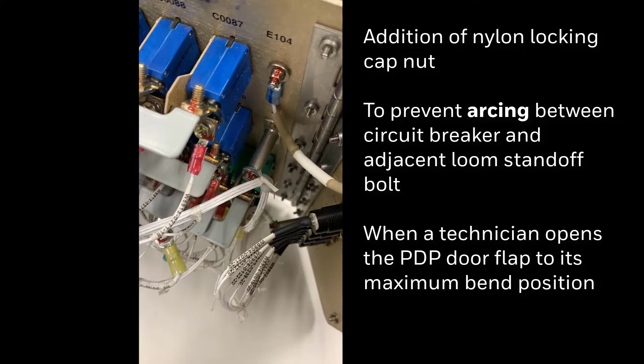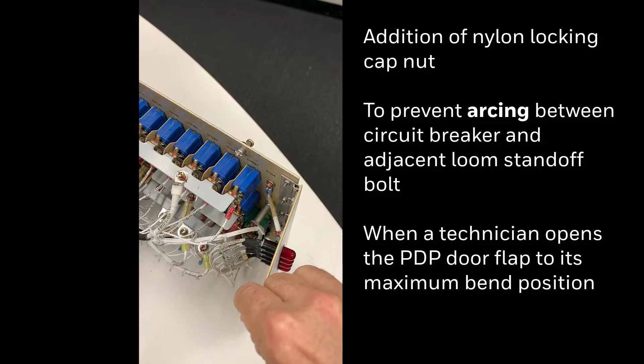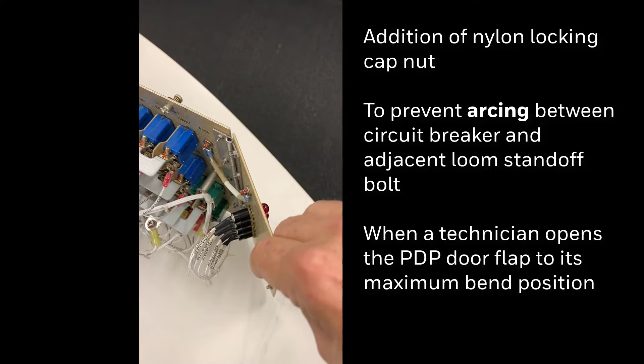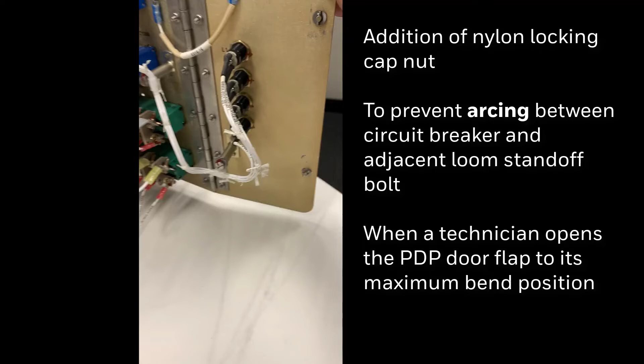This points to the circuit breaker that comes in contact when the panel is bent as shown here. Sometimes maintenance will overbend the panel, causing the powered circuit breaker to touch the standoff as shown, and this causes arcing.